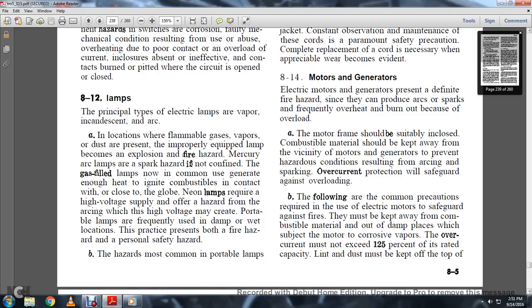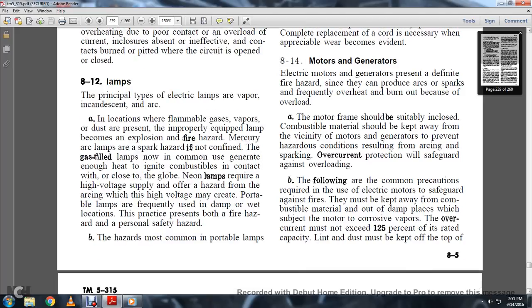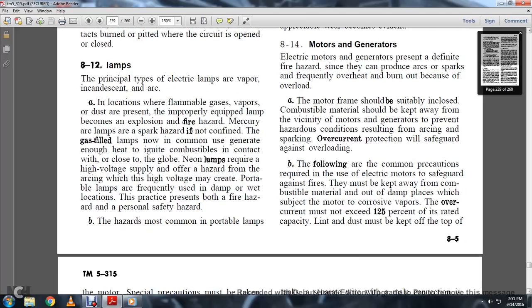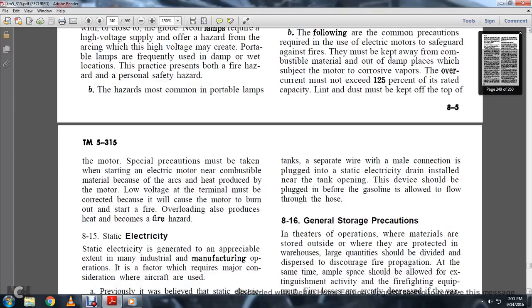The following are common precautions regarding electrical motors: safeguard against rags and fires, keep combustible materials out of damp places, and protect the motor from corrosive vapor. The overcurrent protection must not exceed 125% of the rated capacity. Special precautions must be taken when starting an electrical motor. Surroundings must not be combustible because of the arcs and heat produced by the motor. Low voltage at the terminal must be corrected because it can cause the motor to burn and start a fire. Overloading produces heat that can cause a fire.